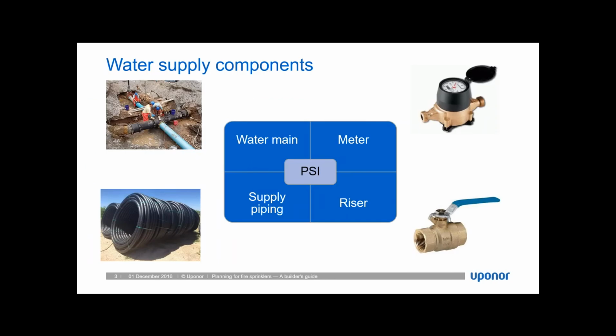So jumping right in, I'm going to first go over the main water supply components that make up the supply for a typical residential sprinkler system. It's going to include the water main in the street. That's the most typical source of a water supply for a home. It's going to be the supply piping that goes from that main into the house. It includes the water meter. And then on the system riser in the house itself, you've got your basic shut-off ball valve. As long as that ball valve is full port, there won't be any noticeable fixed losses, so I won't go into too much detail about that.